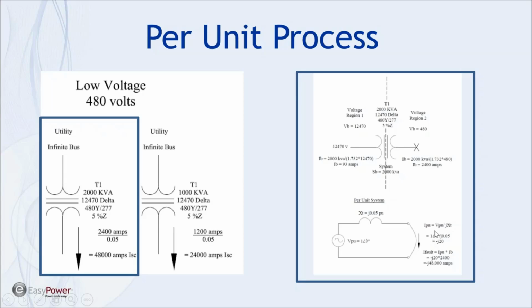So we take 1 angle 0 degrees and divide it by J.05, which turns out to be a multiplier of 20, and we end up with this minus J20. We take that. In addition, I have up in my regions here also calculated my base currents in the 12,470 volt region and the 2400 volt region, because what happens in my per unit system, this per unit current is the same throughout. So if I want actual currents, I have to take my per unit current that I calculated and go back to the particular region and multiply it by the base current.